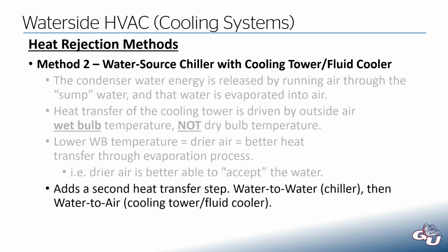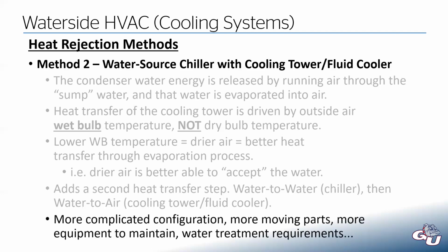And this does add a second heat transfer step. We have our water to water heat transfer process at the chiller, and then we have our water to air heat transfer process at the cooling tower. Significantly more complicated. We have a lot more moving parts, more equipment to maintain. There can also be water treatment requirements. One other thing I didn't list here is the basin water in the cooling tower.